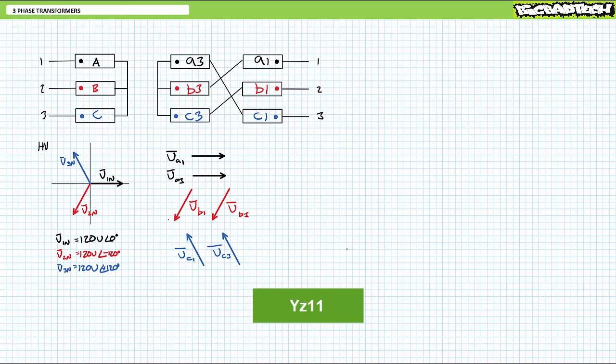This is where it's helpful to have drawn the six low voltage phasors independently. Since we're using the coils A3, B3, and C3 inverted, we can draw these inverted phasors as well. The inversion of A3 is 120 volts at an angle of 180. The inversion of B3 is 120 volts at an angle of 60 degrees. And the inversion of C3 is 120 volts at an angle of negative 60 degrees.